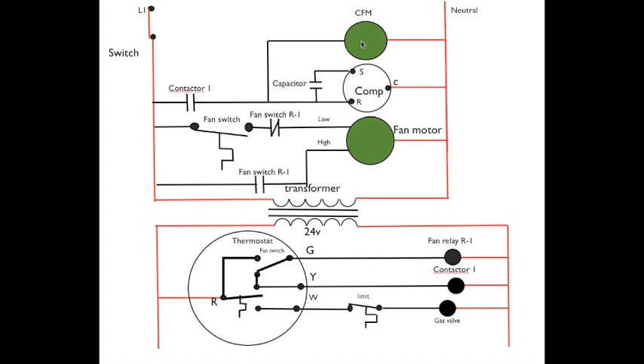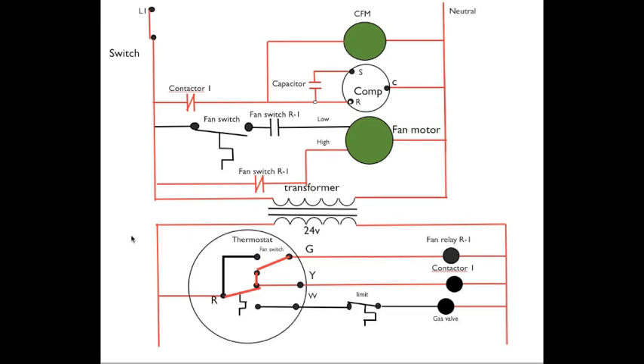So let's see how this one's going to sequence out on a call for cool. Beginning in the low voltage down here at the thermostat, power passes through R through the now closed cooling thermostat. It closes on a rise in temperature, up through the fan auto position, through G to energize fan relay R1 up in the high voltage fan switch.